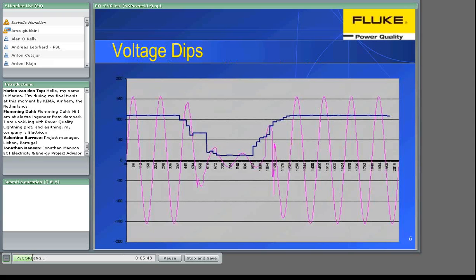The most obvious power failures are complete interruptions and voltage dips as well, where the voltage drops or rises for a short duration. These variations are measured as an RMS value. It means average value over a time which can range from milliseconds to some hours. Causes can come from outside, from the distribution system or other branches of the network, or from inside, for instance, heavy loads switching.